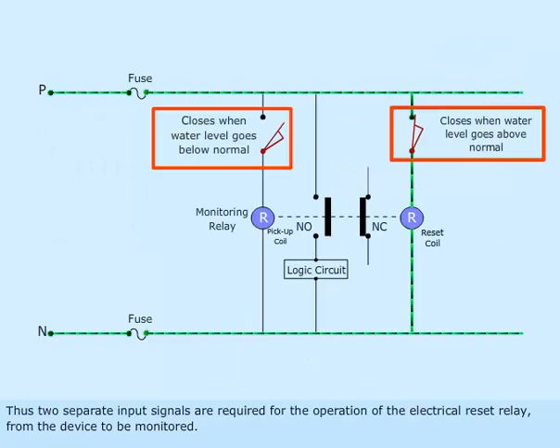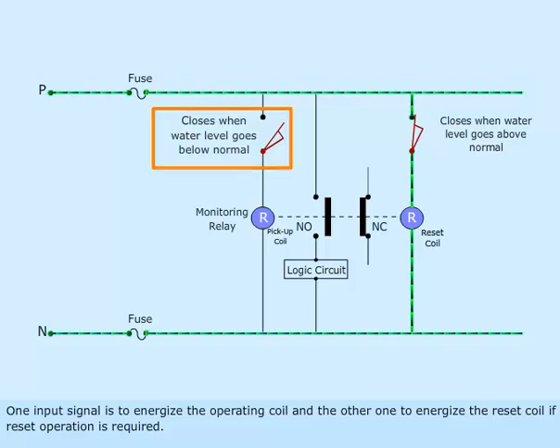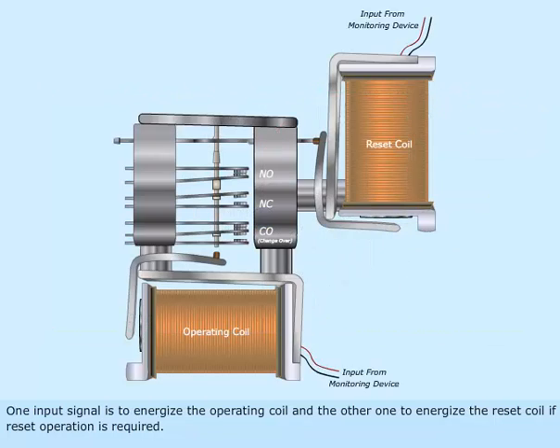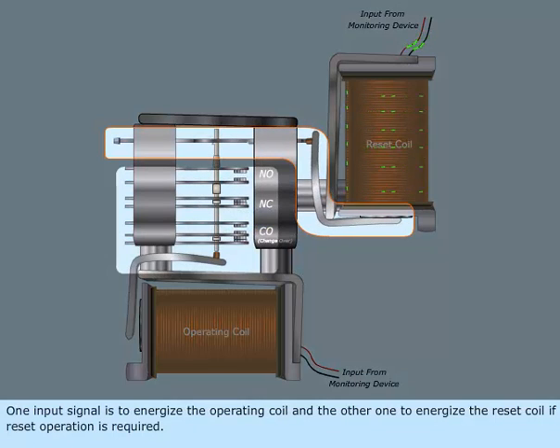Thus, two separate input signals are required for the operation of the electrical reset relay from the device to be monitored. One input signal is to energize the operating coil and the other one to energize the reset coil if reset operation is required.